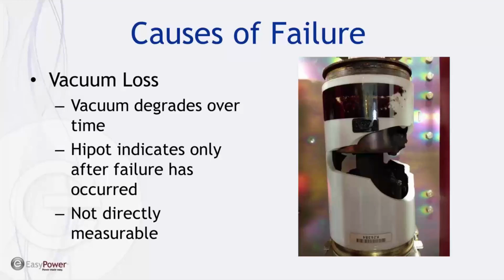There are other things called virtual leaks. A gas permeation would be a real leak, where gas is actually going from the exterior to the interior, whereas a virtual leak can be a couple of things. There are gases trapped inside of the materials that the vacuum interrupter is made of. So when you put these materials into a vacuum, those gases can begin to leak out of the material itself. This is called outgassing. Over time, you have a pretty steady rate of outgassing from the materials that the vacuum interrupter is made of. So you have to be sure that the materials that are used are very high quality, and you want to use materials that have an extremely low gas content.